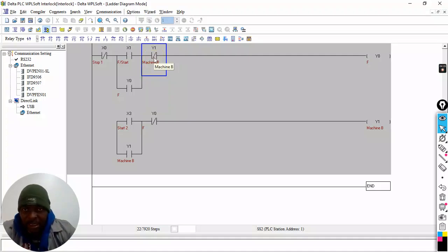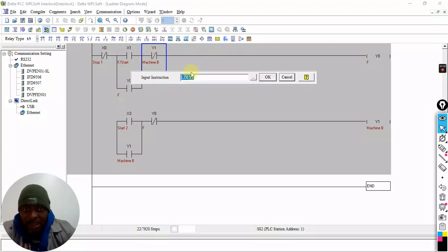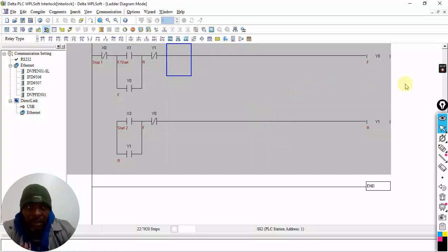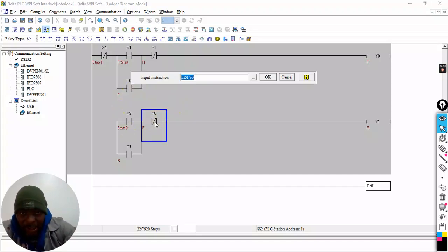And then this here says if the machine is going to run forward, reverse will not allow this. So we'll change this to R for reverse. So we say not another machine, the same machine, but R for reverse. Now if you start here, this is closed, the only break is here. If you start, you are going to start the forward contactor. The forward contactor will latch itself, but it will also say the other one cannot run.